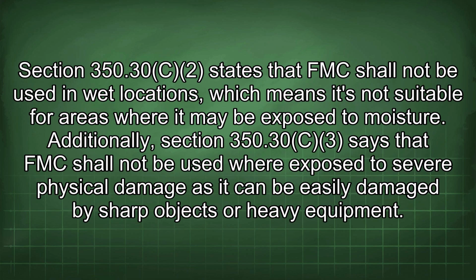Section 350.30c2 states that FMC shall not be used in wet locations, which means it's not suitable for areas where it may be exposed to moisture. Additionally, Section 350.30c3 says that FMC shall not be used where exposed to severe physical damage, as it can be easily damaged by sharp objects or heavy equipment.